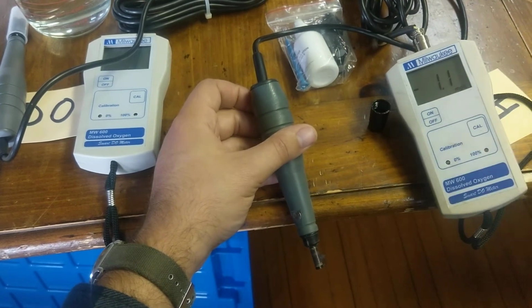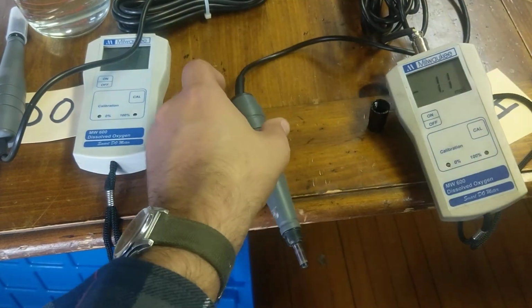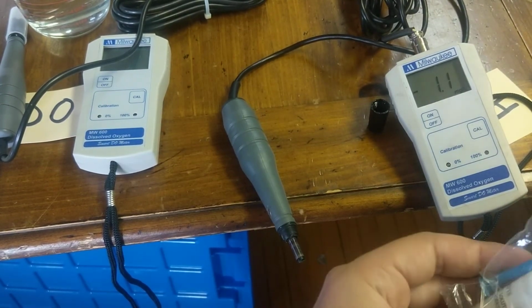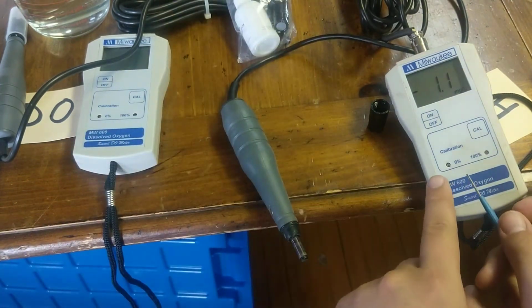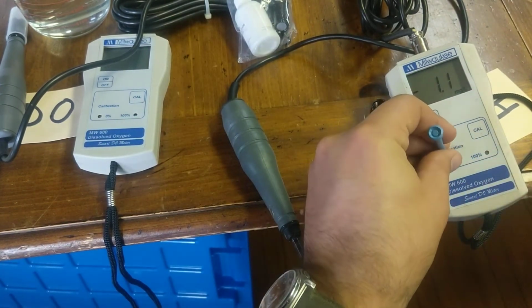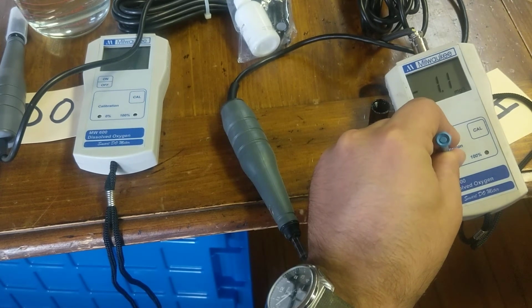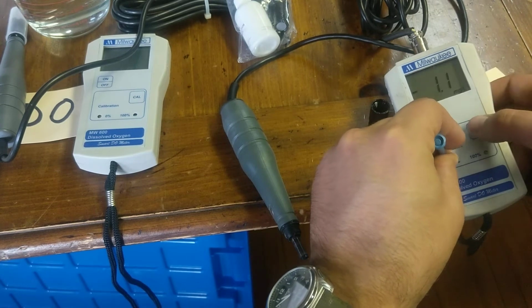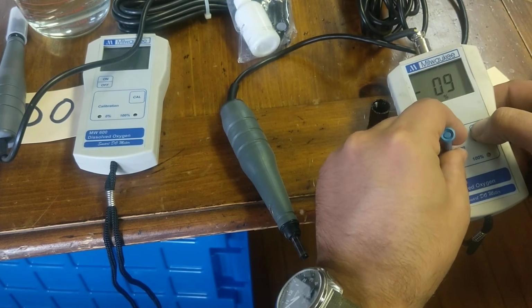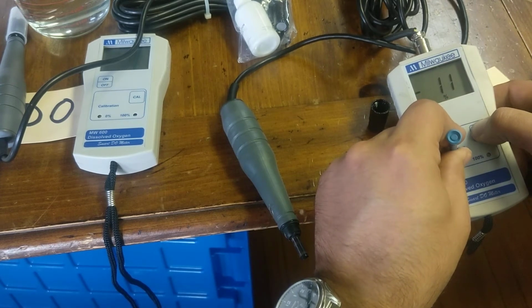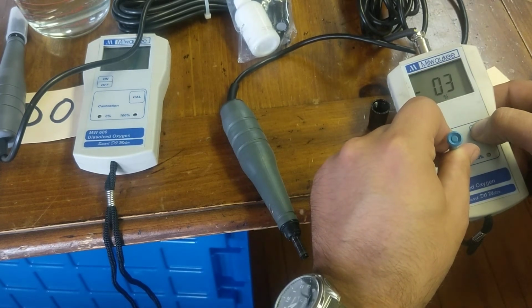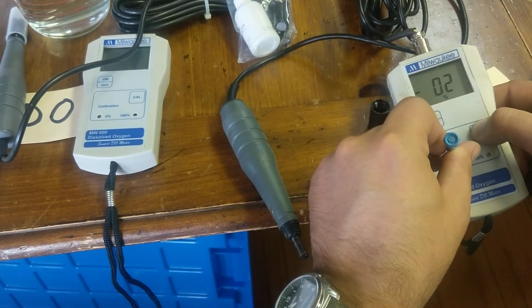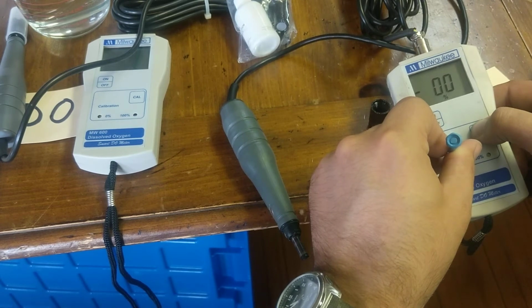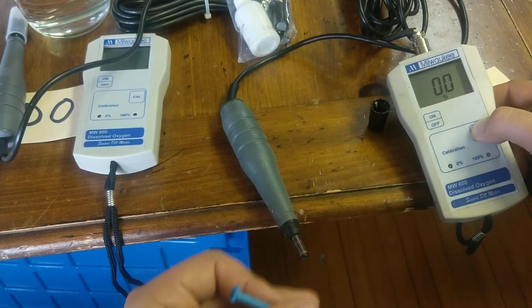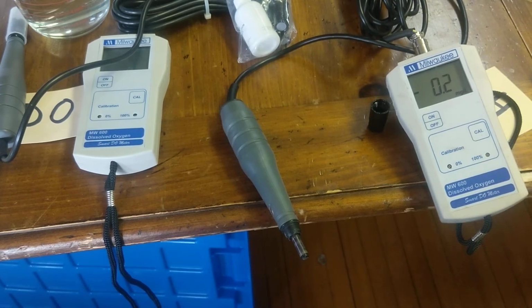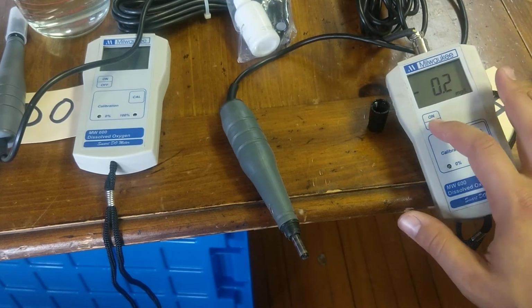So it should read 0. It's reading 1.1 right now. Not so good. So what I'm going to do is basically get the screwdriver. You want to go under the 0 calibration screw and just turn it so that it reaches 0. So I'm going to turn it. Oh, you may need to press the cal button. Yeah, there we go. You press the cal button and go until it's 0. There we go. We're at 0 right now. Perfect. Once that's all set, you can then turn it off.